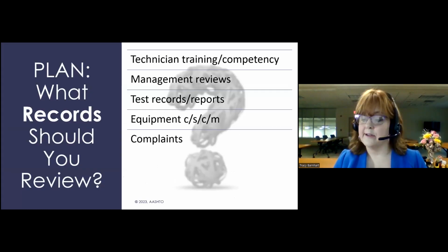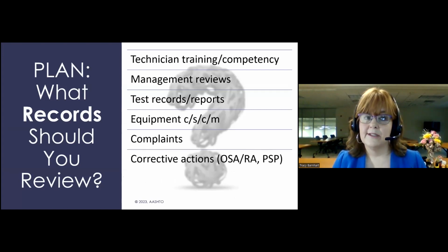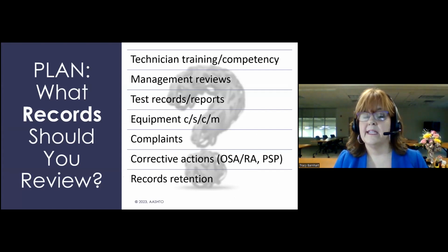You can review records of complaints during internal audits, corrective actions from your on-site or remote assessments, and low ratings that you received on proficiency sample programs, and records retention. If you say you're keeping records for at least 10 years, verify that. Pull some records to make sure they're at least 10 years old.